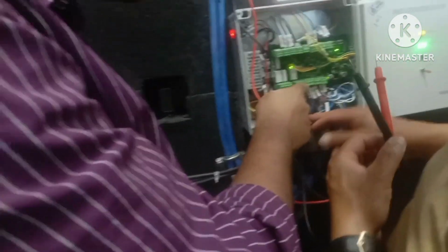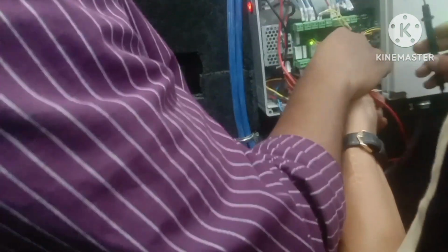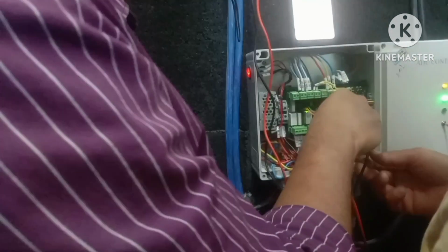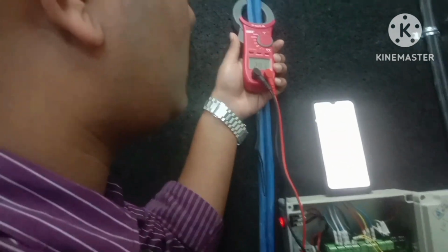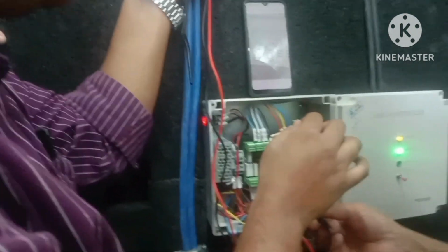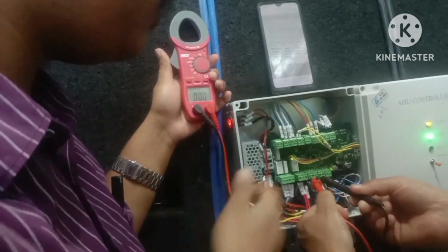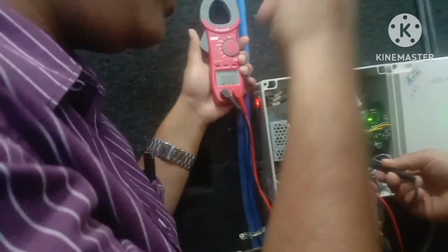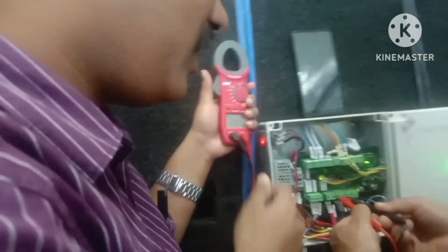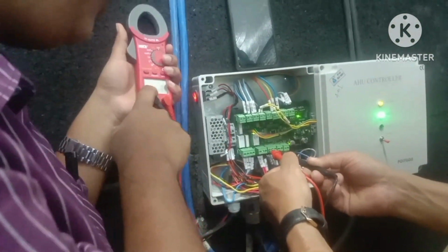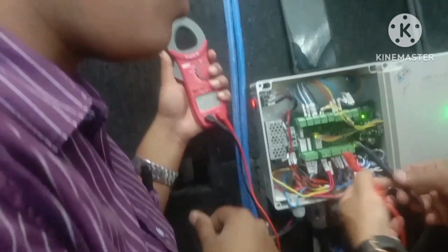Please touch here. This one is for positive. The negative can be taken to ground also, no? Yeah, that is neutral. Then I can try from earthing also, no? Sure, I'll try from earth. From earth it is not giving. Earthing will not show, basically now we have given the neutral. Their earthing is not connected. If the neutral is not given, then we can give it to the earthing. So you can see the 28 volt is now going.